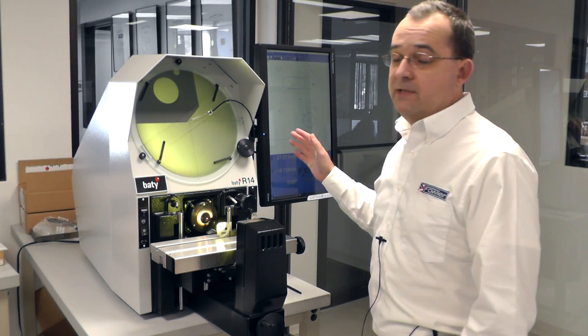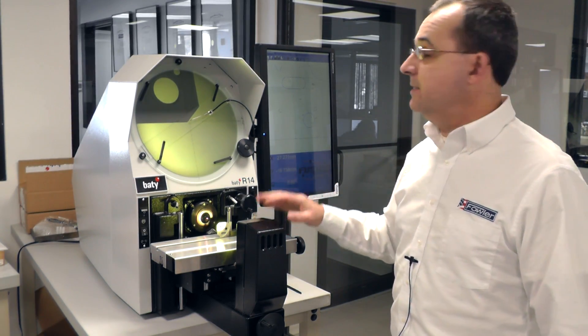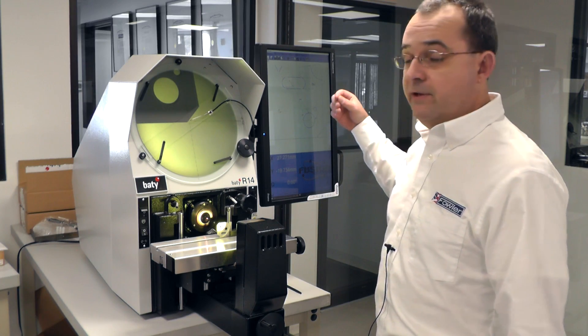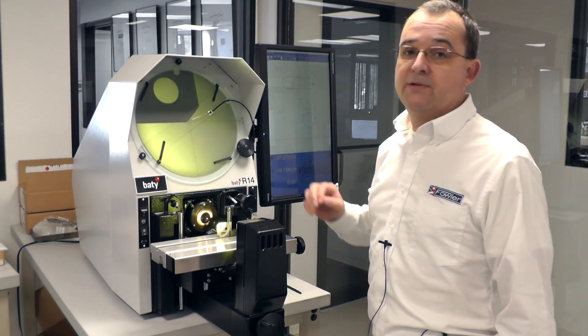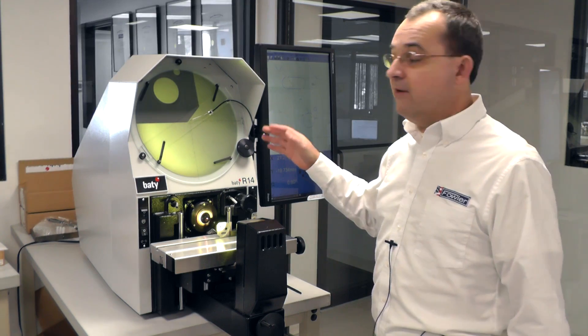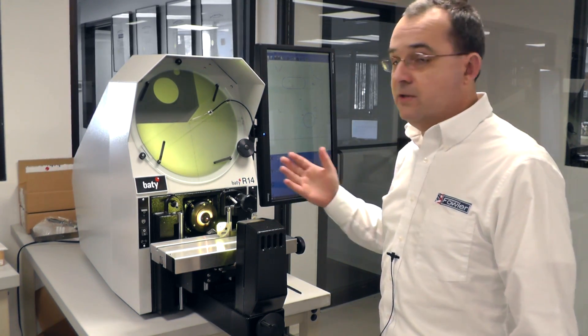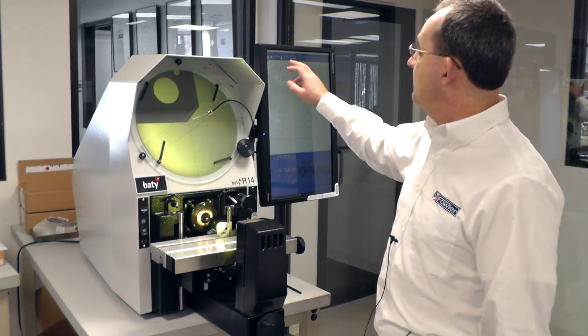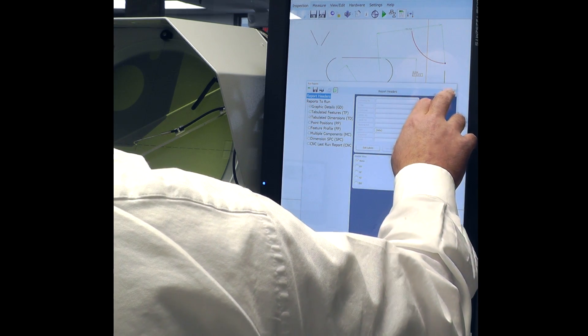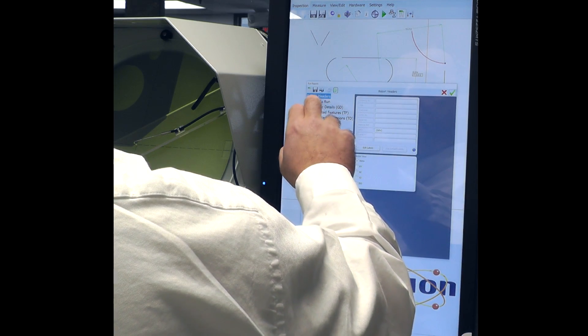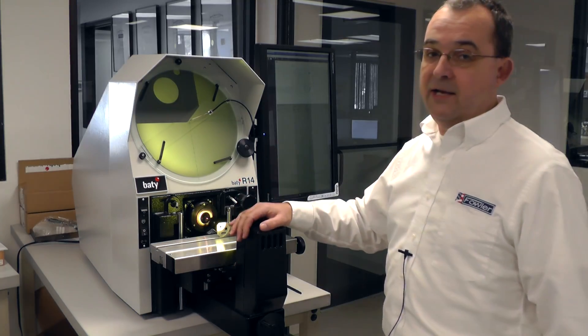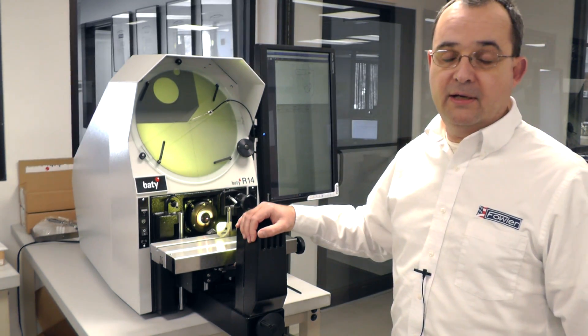One of the big advantages to going to a PC-based software on an optical comparator is the ability to take the data that you can measure and construct on virtually any readout, but this one specifically. You can export that data quite easily because we're using a true Windows 10 PC here. You can export it via the Ethernet port, USB, or you can dump it into an Excel file that can be resident on this PC. So you have the ability to generate quite impressive reports, and those reports can be in a variety of different types — saved online or offline depending on what you need for your SPC requirements.